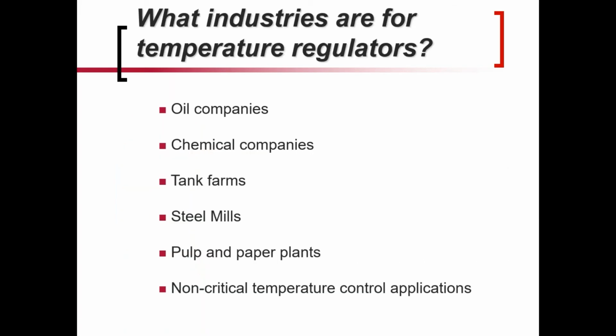And where do we see these applied? As Chris said, we've been manufacturing these for over 50 years, and this is one of our legacy products as Jordan Valve. So we see these across a really broad industry: oil companies, refining companies, chemical manufacturers, anybody with a tank farm. It's an inexpensive way to maintain tank temperatures, steel mills, pulp and paper plants, and non-critical temperature control applications. And what that means is if you have to have very precise temperature control, a mechanical means of doing that is not always going to be the best approach.